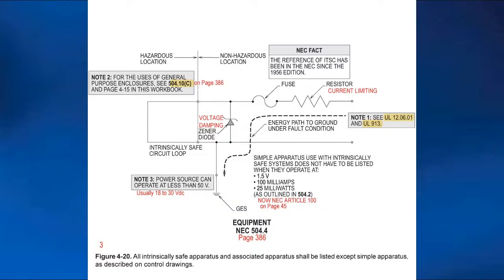So I have a question. I was working at a peanut butter and jelly sandwich factory, and they had a lot of flour. So we had fire alarm devices that we had to install in that area, which is a Class 2 Division 2 area. Well, it was my understanding that those would be considered intrinsically safe because those devices operate under 50 volts.